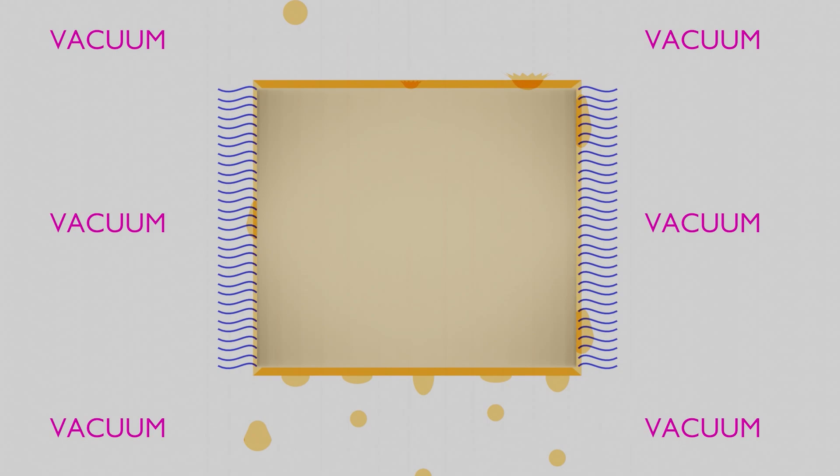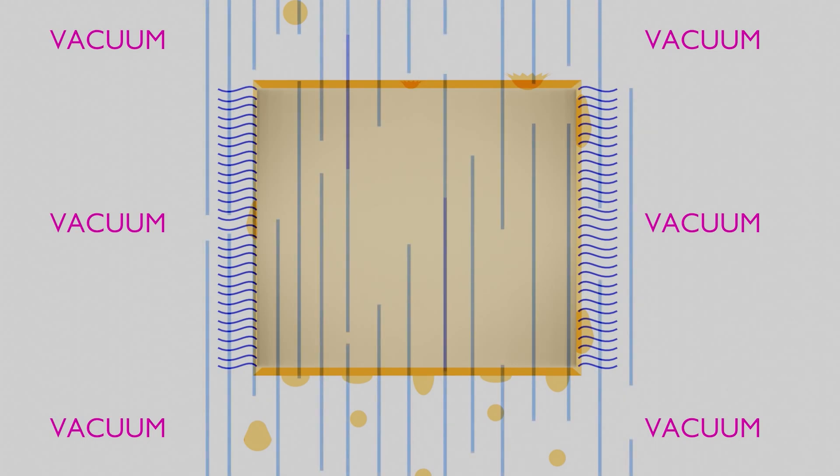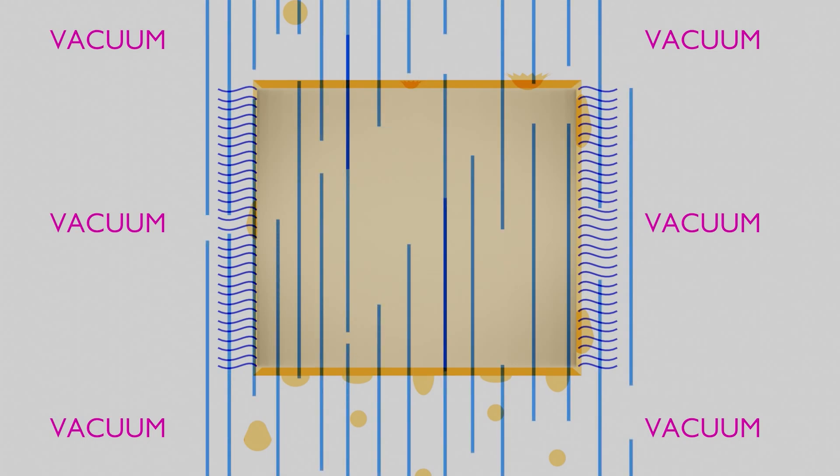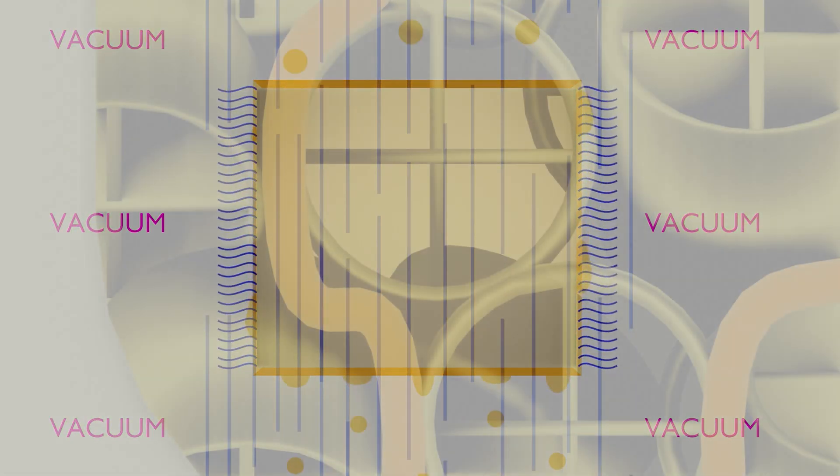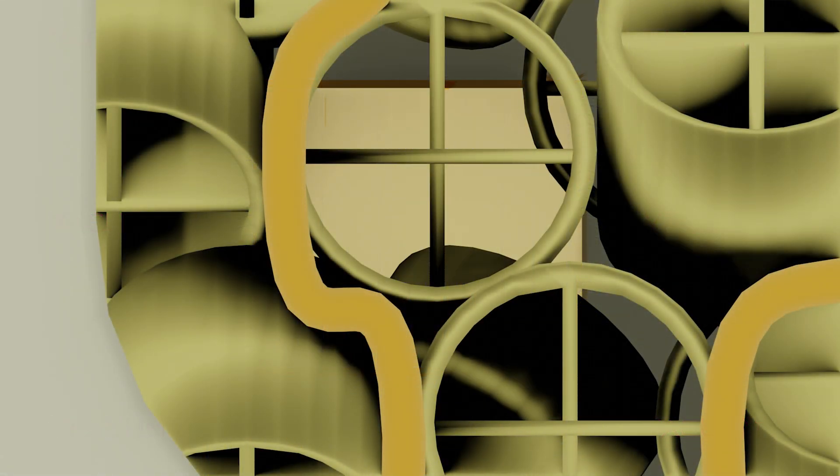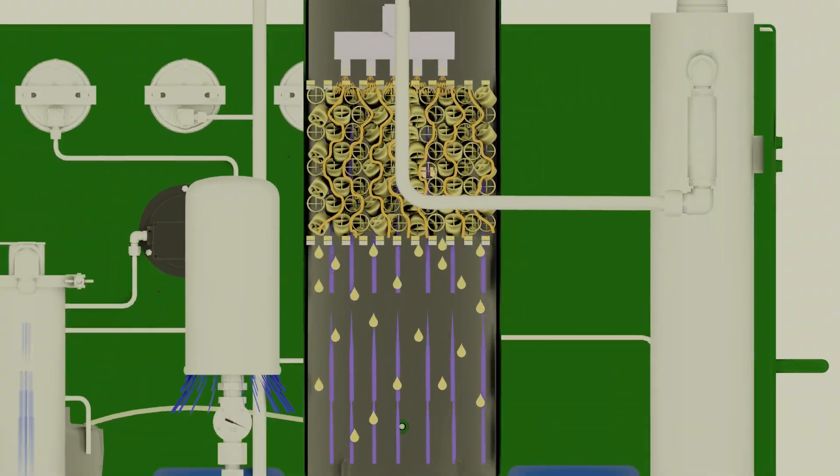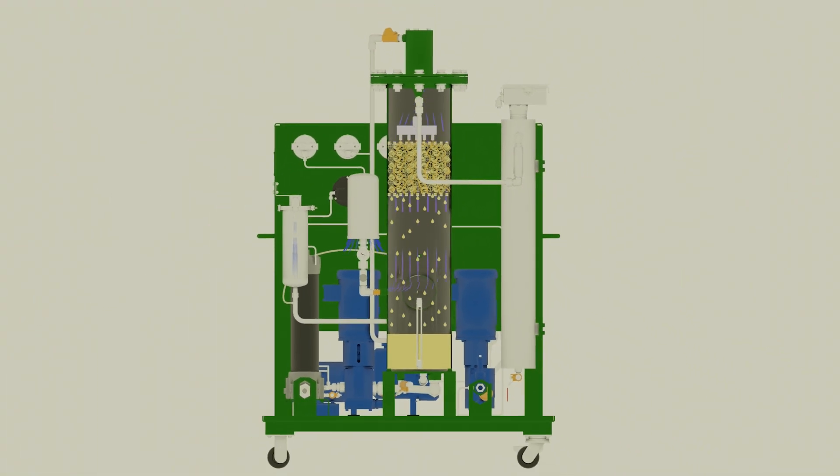Once water dehydrates out of the oil, it is absorbed by the dry sweep air being pulled through the vacuum tower, while oil remains in the vacuum tower due to its higher evaporation temperature than water. Once water vapor is extracted by the dry sweep air, it is expelled to atmosphere by the vacuum pump.